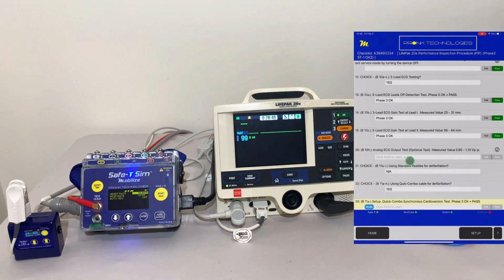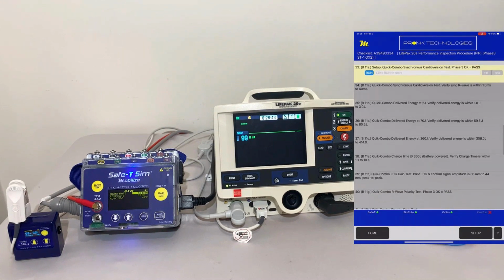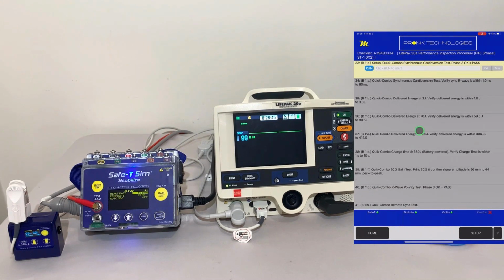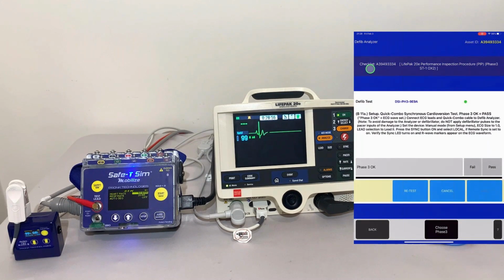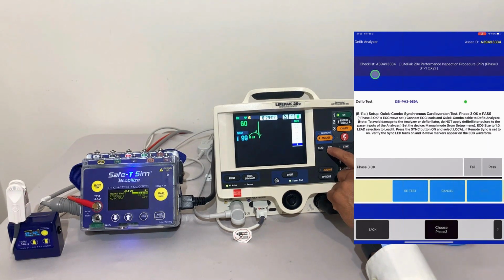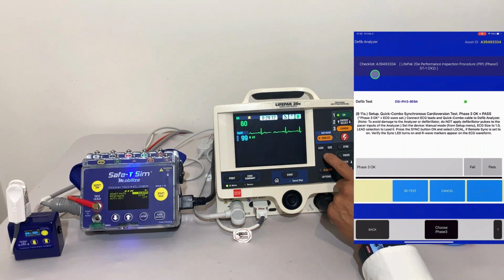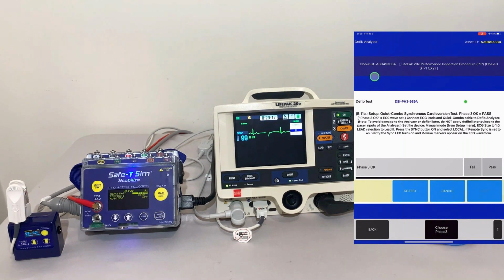As you can see here, now we can see all the steps required that we need to do. The next step, according to the LifePak 20 performance inspection procedure, is to run a synchronous cardioversion test. It's going to set the ECG to a particular shape. I want to set the size back to normal, back to what it was before we did our gain tests. So we've done that. And we want to confirm that we are set for lead 2 and that we are verifying that our ECG waveform is correct.